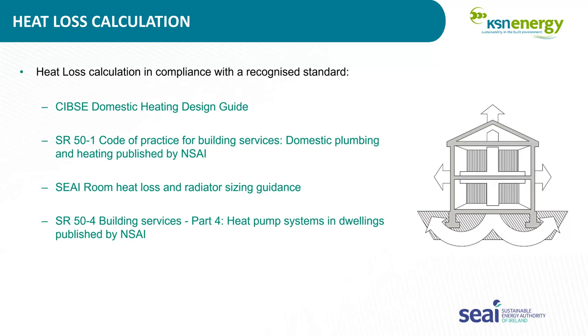So we assume that there's no heat loss through the floor there. And the apartment above will have heating, so we assume there's no heat loss there. So the demand for heat in a room can be different, and we need to be a bit more accurate about how we do it. And rules of thumb are no longer sufficient.